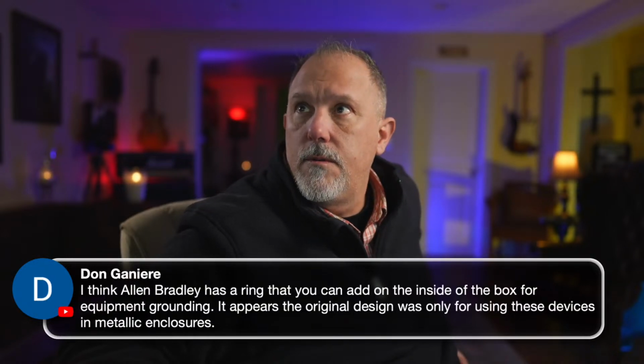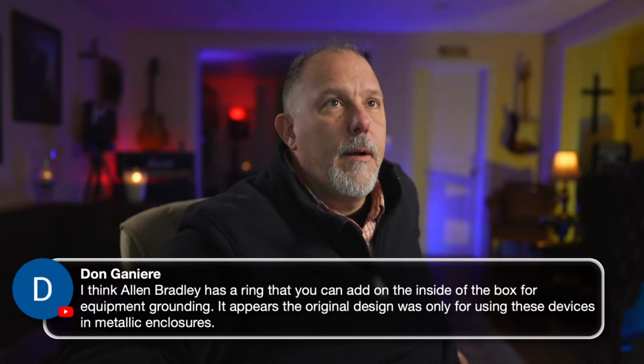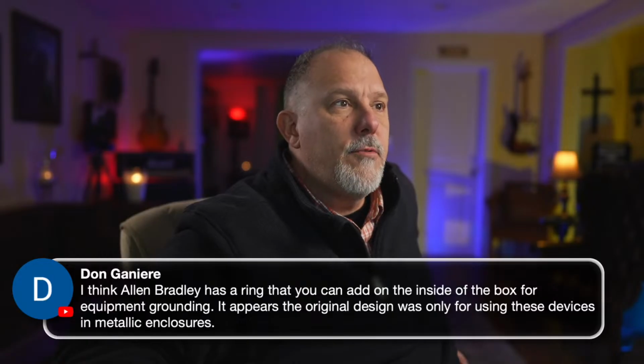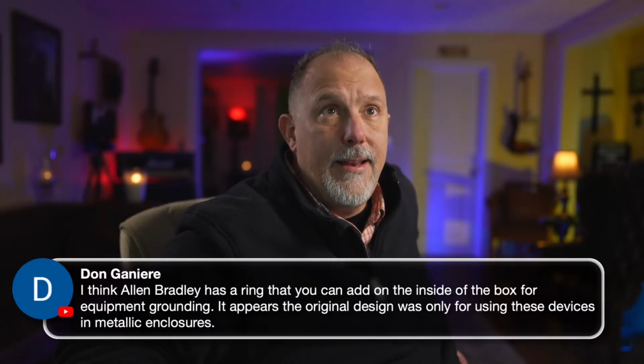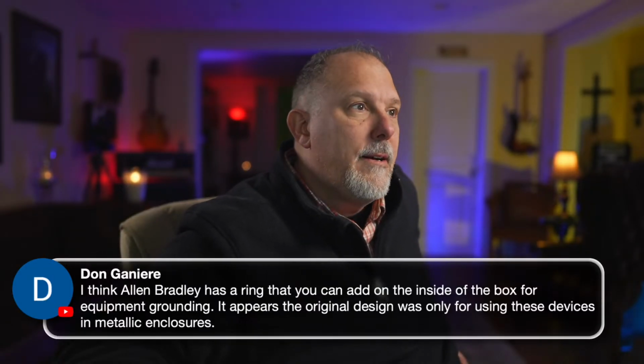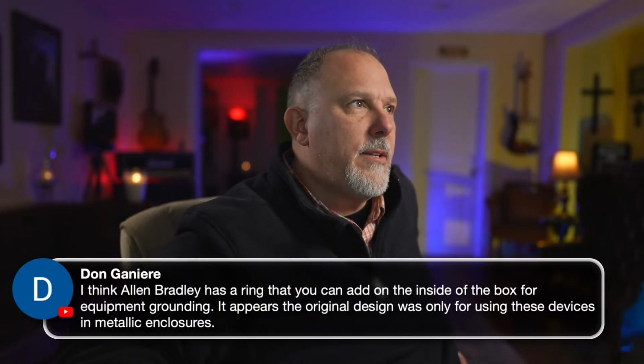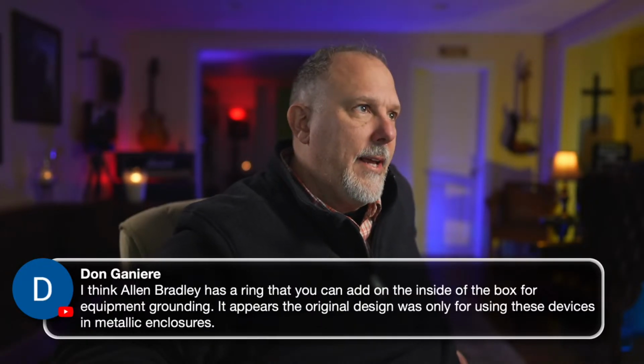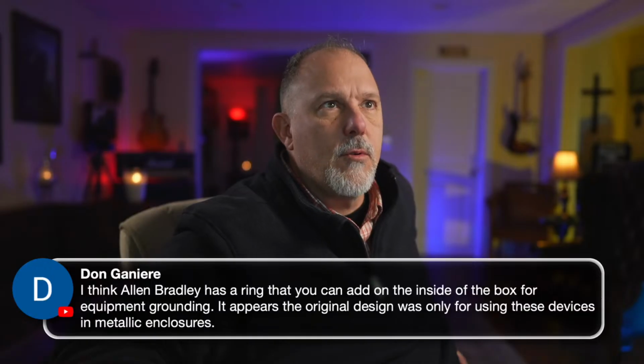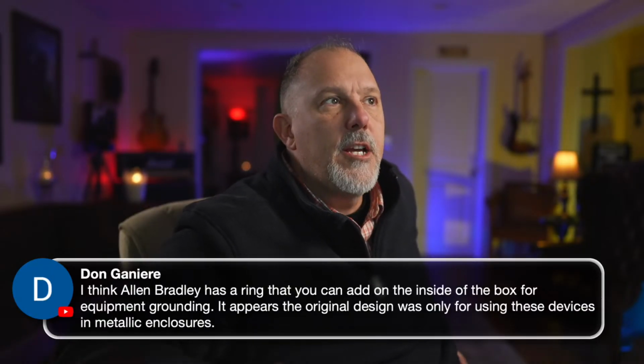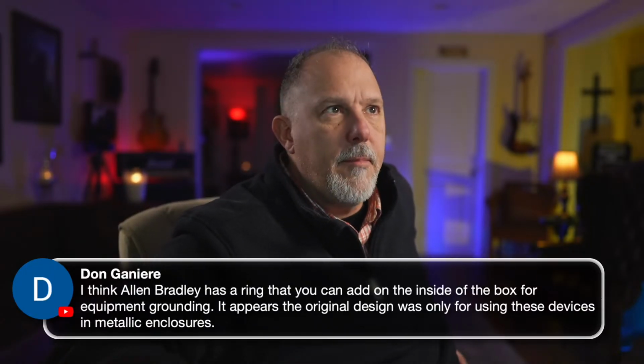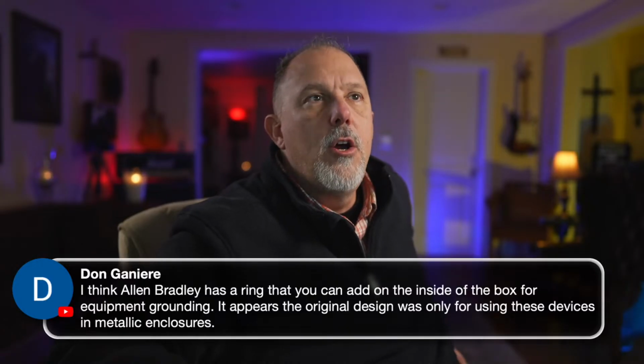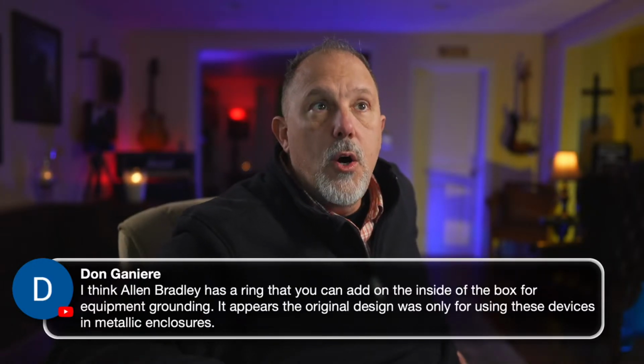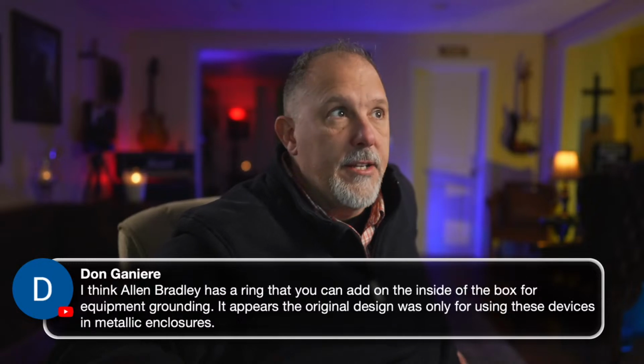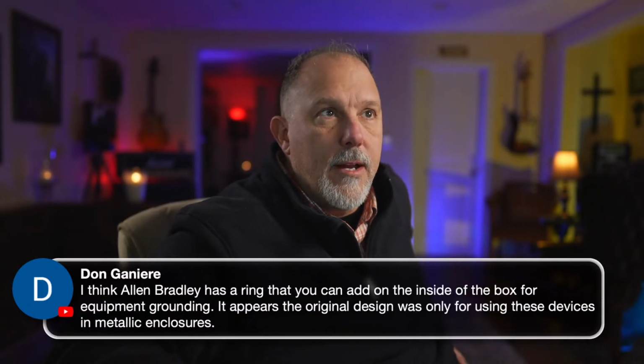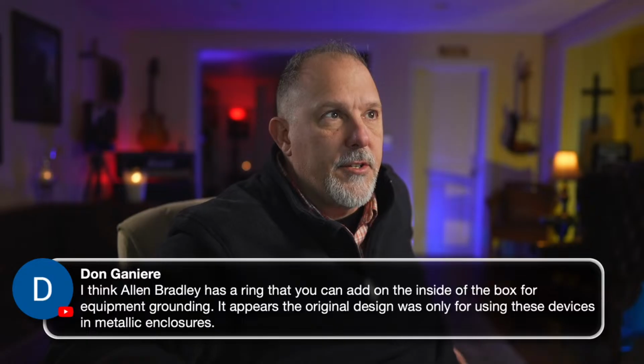go to 250.110, I think it is. I'm in 250 and I can't remember. Is it 110? 110. Equipment fastened in place, fixed or connected by permanent wiring methods. Exposed, normally non-current carrying metal parts of fixed equipment supplied by or enclosing conductors or components that are likely to become energized shall be connected to an equipment grounding conductor under any of the following conditions.